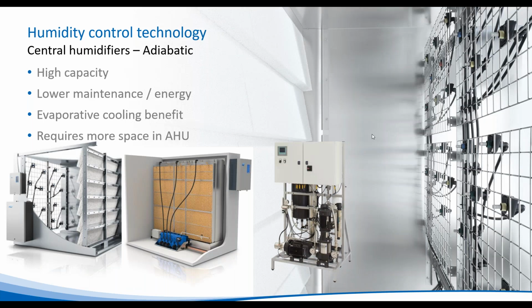But there is another way. Instead of putting steam in, we can use an adiabatic system. Now, an adiabatic system evaporates water in the airstream. So it uses the heat energy of the air to evaporate the water. What that means is that we need to preheat the air before the air hits the humidifier. So as air hits the humidifier, it evaporates water. So we see an increase in relative humidity, but a decrease in dry bulb temperature as we're sucking that heat energy out of the air to change the state of that water from a liquid into a gas.